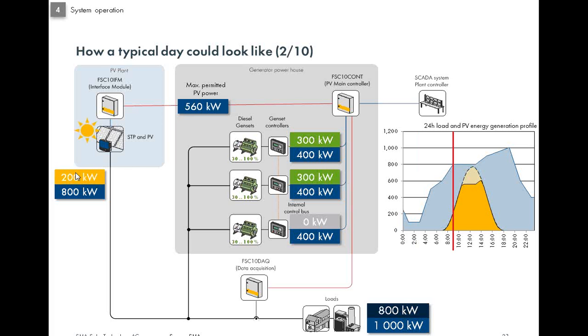Okay, now let's flash forward to 9 o'clock in the morning. The sun has woken up and your PV system is giving you 200 kilowatt. And now your load has also increased to 800 kilowatt. So what happens? Your GCU will essentially make sure that the load is divided between the two gensets and you'll end up getting 300 kilowatt from DG1 and DG2. Now, as the sun continues to rise, it's 11 o'clock and you have much more radiation and your solar system is giving you 560 kilowatt. Because of this, the DG sets see a lower apparent load and they will only give you 120 kilowatt, and this is where your fuel saving is coming in.